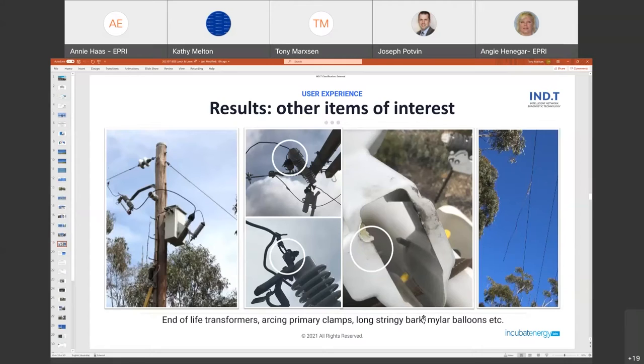Here's a few more cases. The one on the left is a transformer that got hit by lightning. Even though it's got a surge diverter on it, it was obviously damaged, had an internal problem, and that was generating a lot of radio frequency signal.